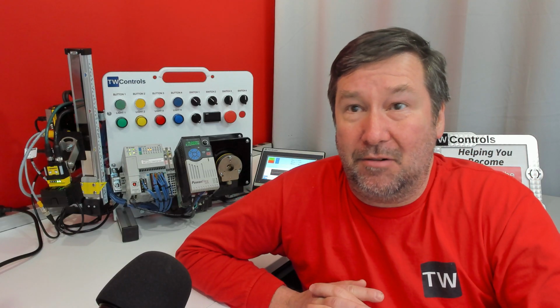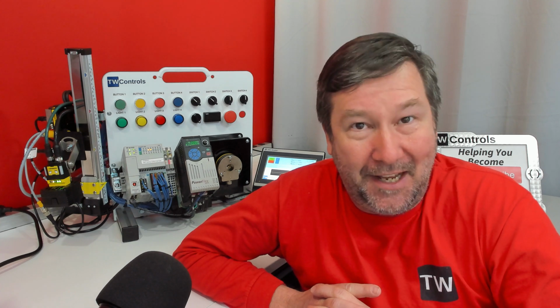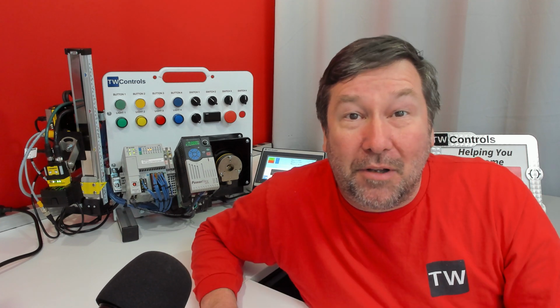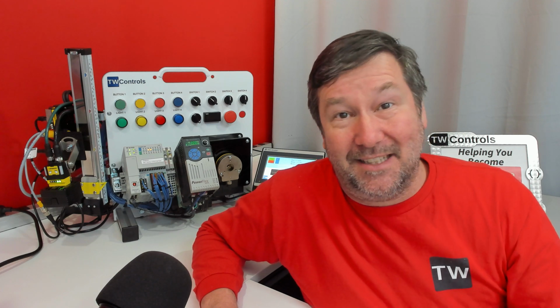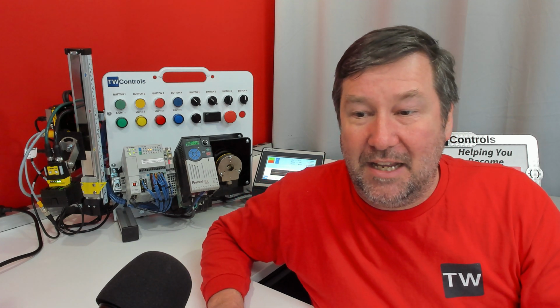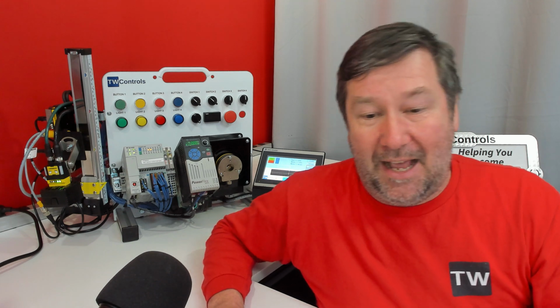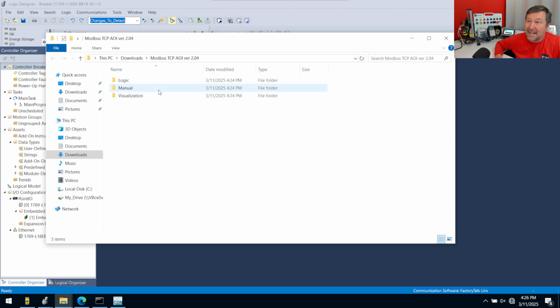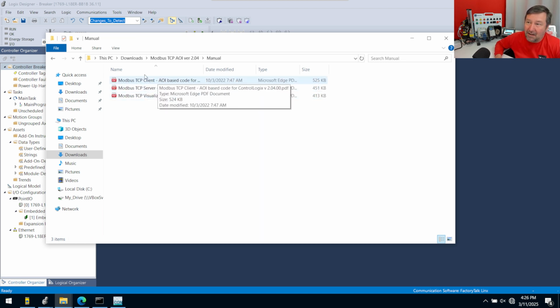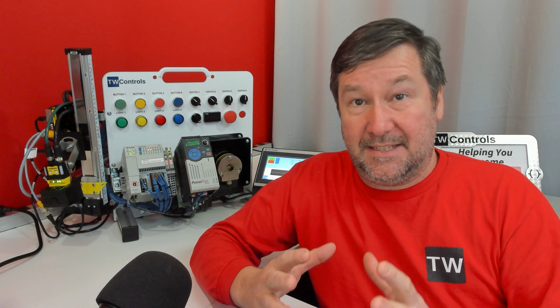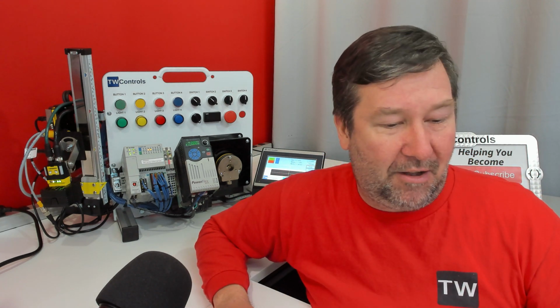Now, a lot of you are probably thinking, well, wait a second, I didn't think that Studio 5000 had Modbus TCP in it. Well, it doesn't, but Rockwell Automation wrote an add-on instruction and it's in their sample code library. So just go to their sample codes and you can download the Modbus TCP AOI. I already have videos on exactly how to download it and everything, so I'm not going to go deep in the weeds on that part, but mainly in the manual, we have Modbus TCP client, Modbus TCP server. And in the case of the Siemens 3VA6, or more specifically in the case of the COM 100 module, it is the server. We are going to be the client to it.